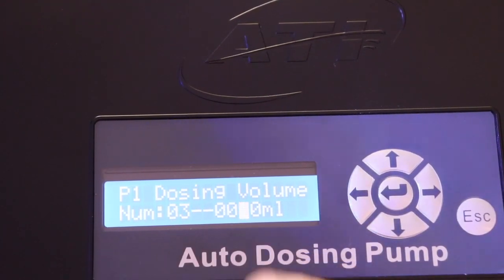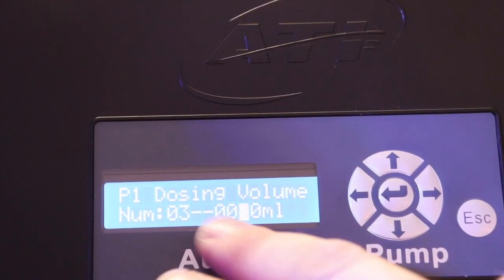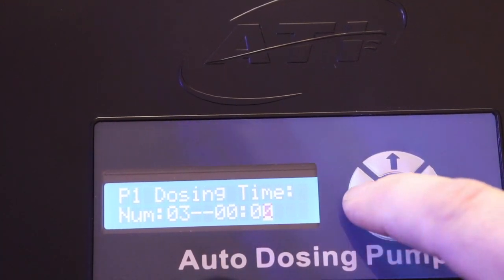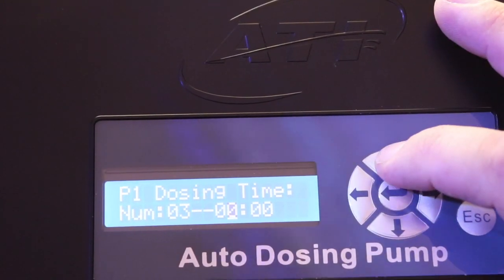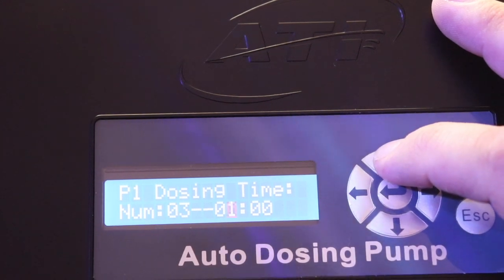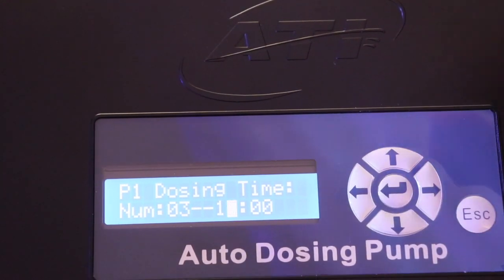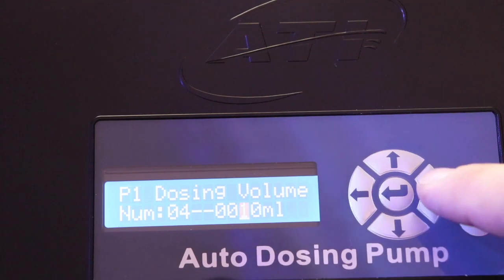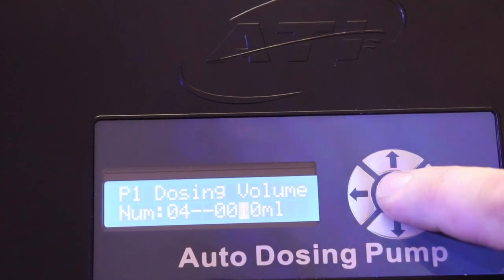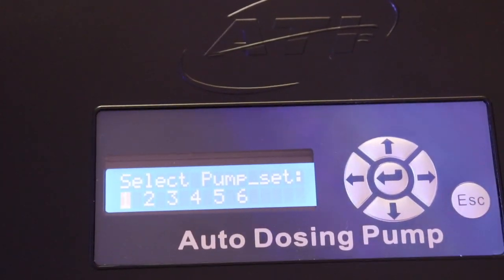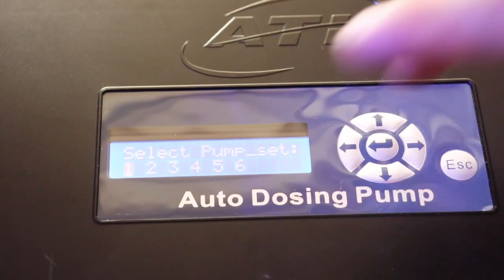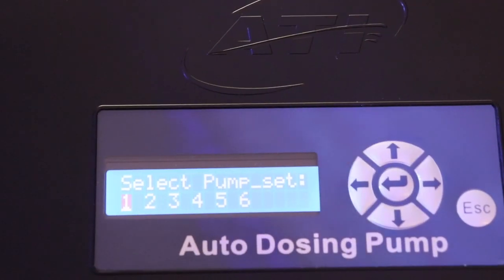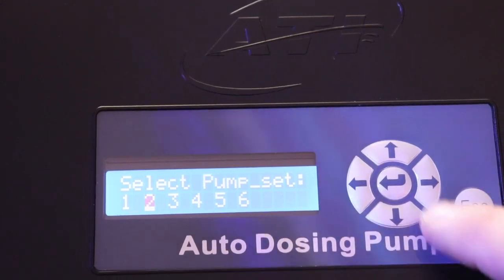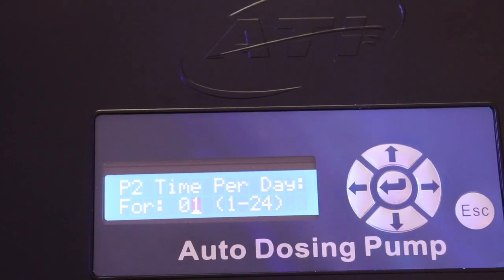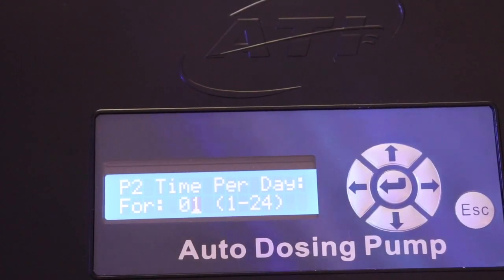The third dose, which we didn't get to set the time on this one, is 10 milliliters again. And we're going to change that time because it skipped by it the last time we did it. So we're going to have this one go at 2 p.m. Then our fourth dose for the day is 10 milliliters at 3 p.m. And that's essentially how you would set up every single pump. So after setting up that first pump, go to pump 2 and do the same thing all over again. Pretty easy to set up and maintain.